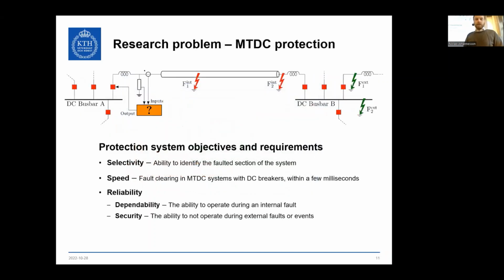That leads to the research problem, which I tried to formulate with this yellow box with a question mark. The research question is: if you have DC breakers in a DC network, when do you trip — when do you decide that the breaker should open? In this example, where we have DC breakers on all the lines, you should operate the 2 internal red ones. However, the green ones are external, meaning they should be cleared by different breakers, so the line protection on the left side should not operate. That's the selectivity part.